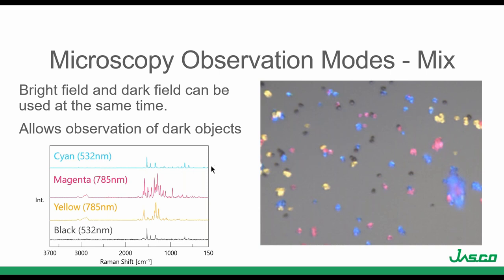We have a mixed observation mode where bright and dark field are combined, so everything can be observed — the dark areas as well as the colored ones. In this mode, using the auto stage, we can go exactly to the point where we want to make the measurement. You can see the Raman spectrum of the yellow particle, the magenta one, or black — those are measurements made using different laser lines.